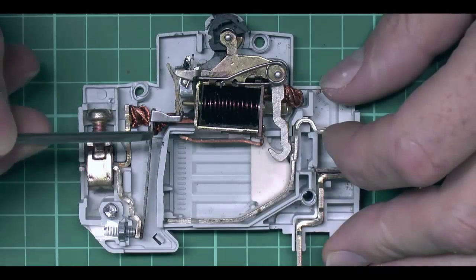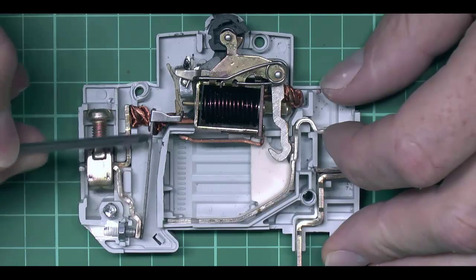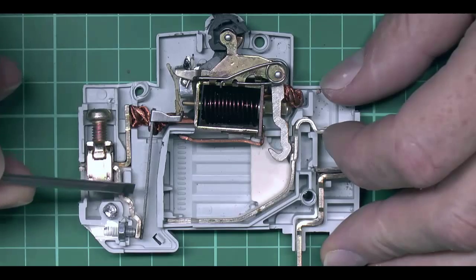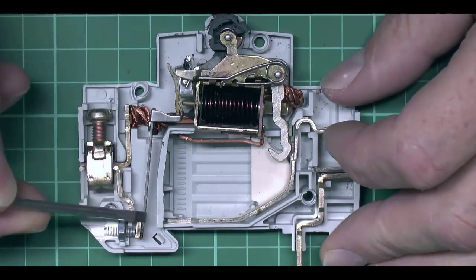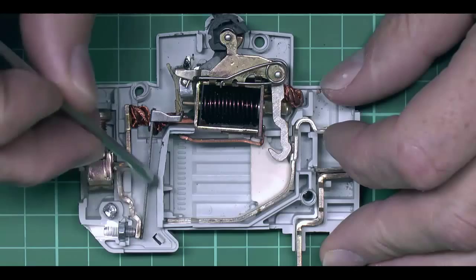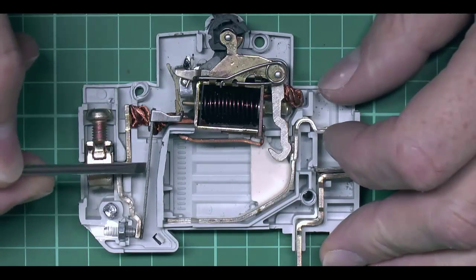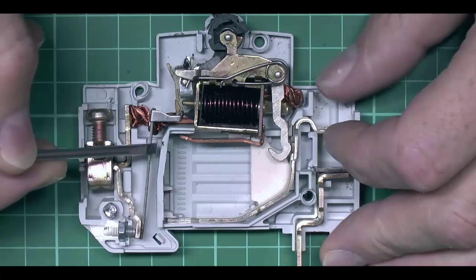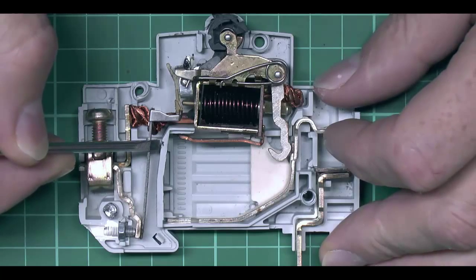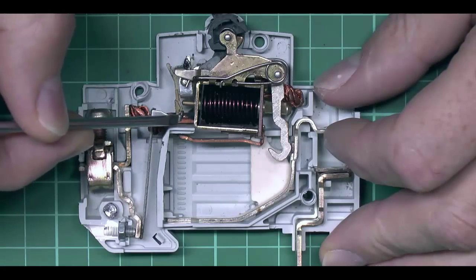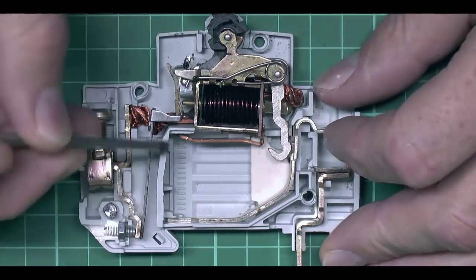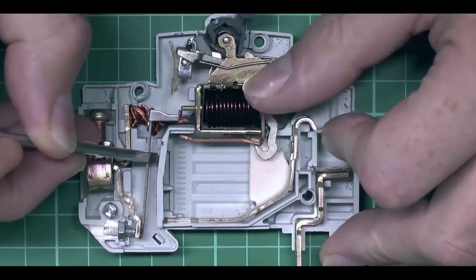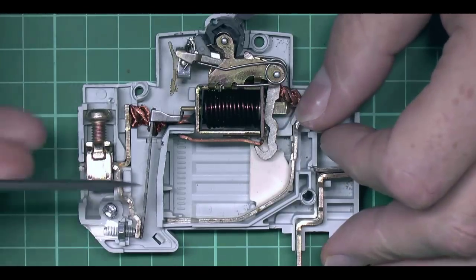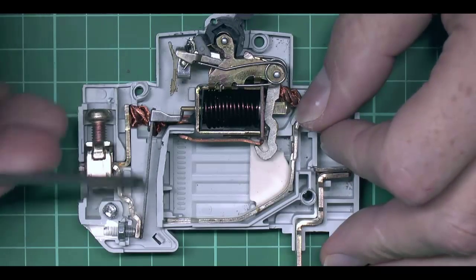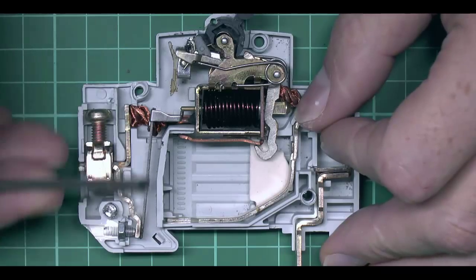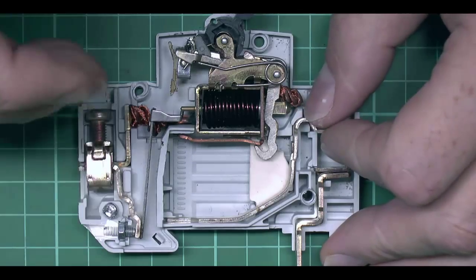Now the other tripping part here is this strip, and this is a bimetallic strip, similar to the type also used in thermostats, and as the current passes through here, it will cause the strip to heat up, and because it's made of two dissimilar metals, one side of it will expand at a different rate to the other. This will cause the strip to bend, and as it bends, of course, it will pull on this little lever here, and if it heats up enough and of course bends far enough, then it will cause the device to trip and switch off. And of course this is selected depending on the rating of the device, so that if the current exceeds a predefined level, then of course that will disconnect the device.